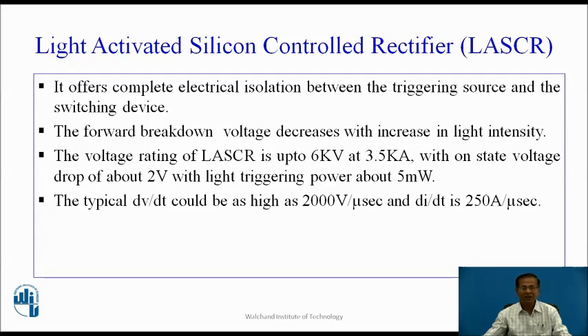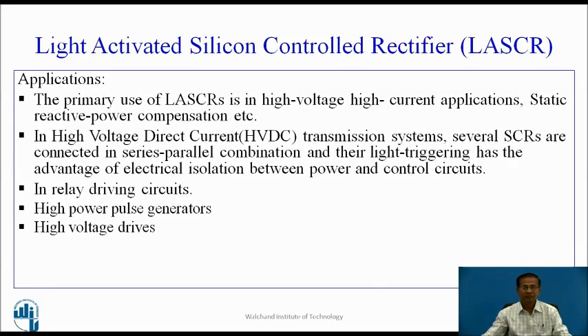The typical dv/dt could be as high as 2000 volts per microsecond. The primary use of LASCR is in high voltage, high current applications and static reactive power compensation. In high voltage direct current, that is HVDC transmission systems, several SCRs are connected in series-parallel combination, and their light triggering has the advantage of electrical isolation between the power and control circuit. Applications also include relay driving circuits, high power pulse generators, and high voltage drives.